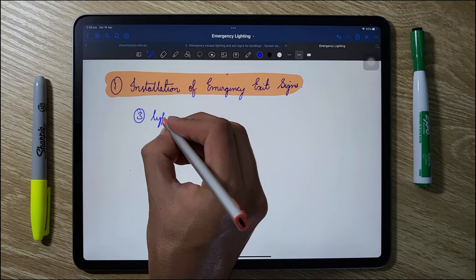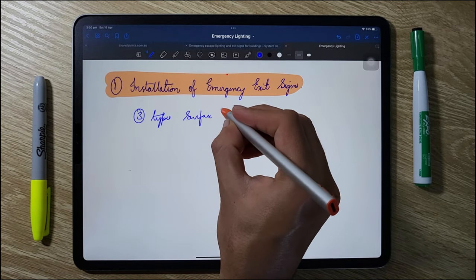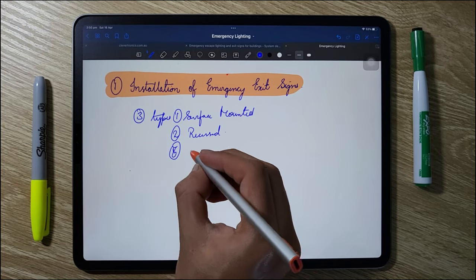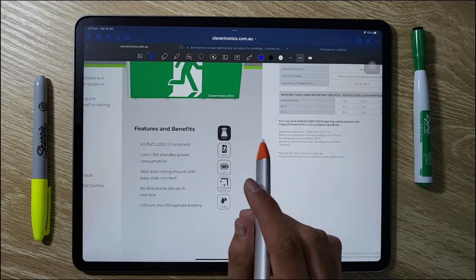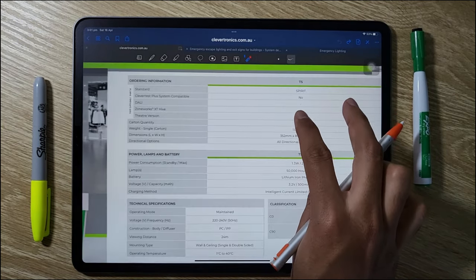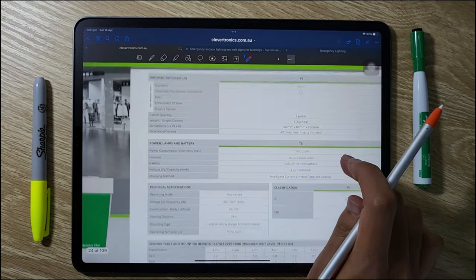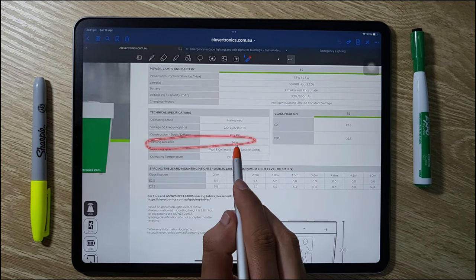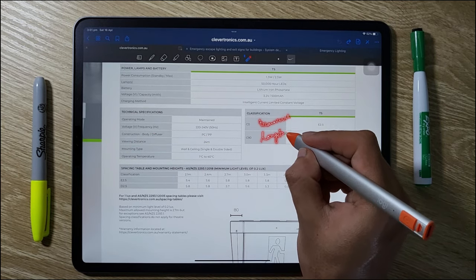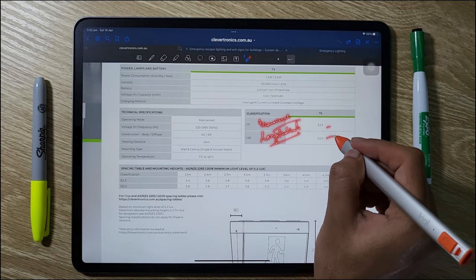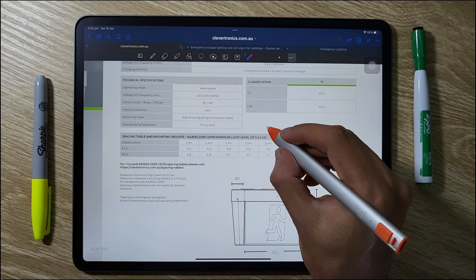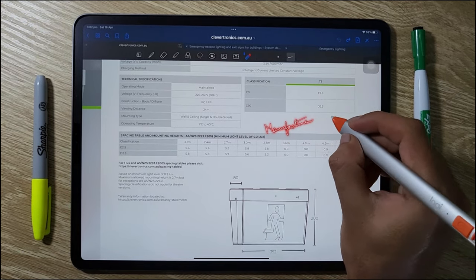Now let's begin with the installation of emergency exit signs. There are three types: surface mounted, recessed, and suspended emergency luminaires. Let's go through the manufacturer data sheet for emergency exit sign selection. There are two main things to consider: the first is maximum viewing distance, and the second is classification, which depends on the longitudinal and transverse planes of the luminaire.